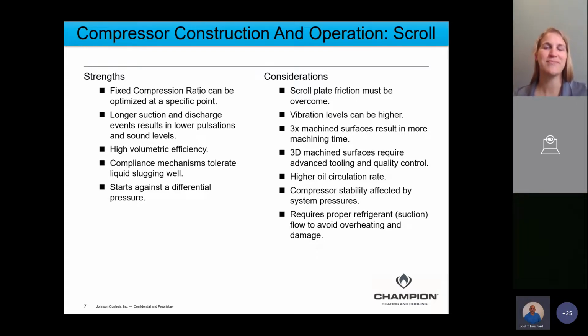It's not a 100% fix, but basically what happens when a compressor shuts down, in other words, when the thermostat is satisfied and the outdoor unit shuts off, is there's going to be a pressure differential between the high side and the low side for a while, even after the compressor shuts off, until the pressures in the system start to equalize through components like a reversing valve and an expansion valve. During that time, we need to let the compressor set a little while in between cycles.